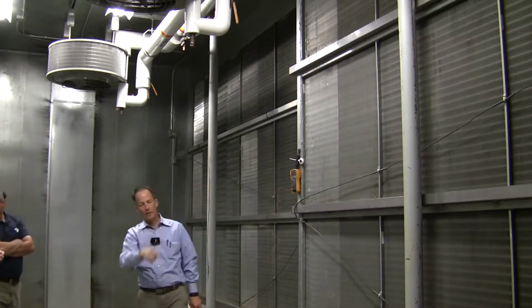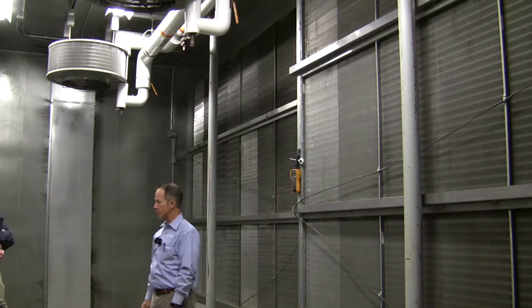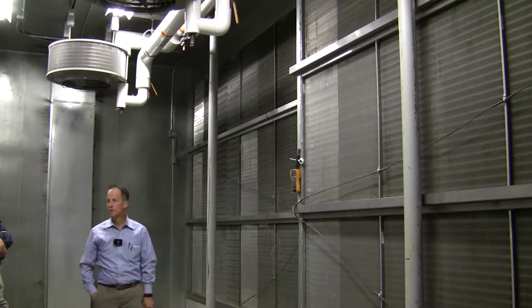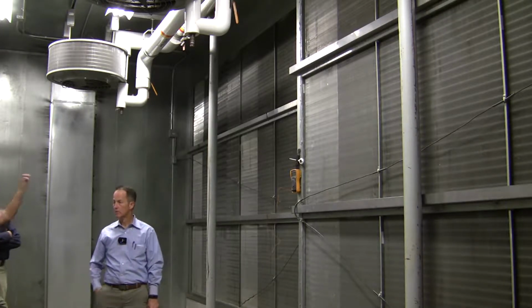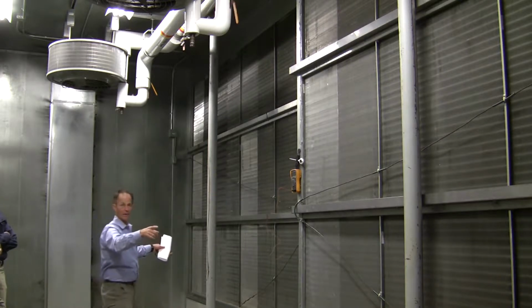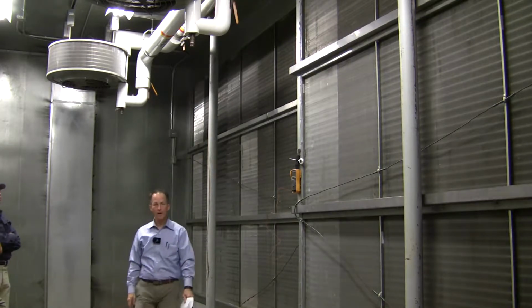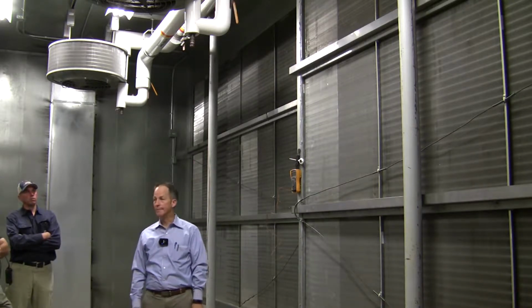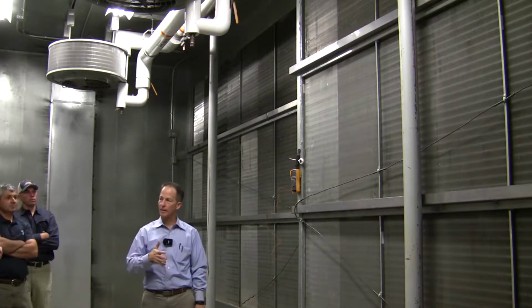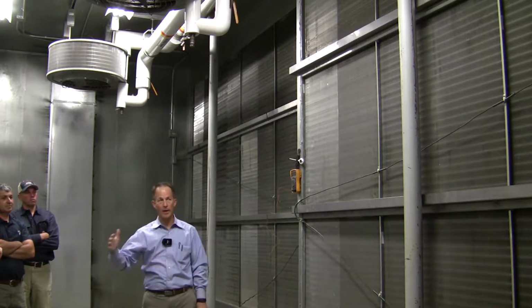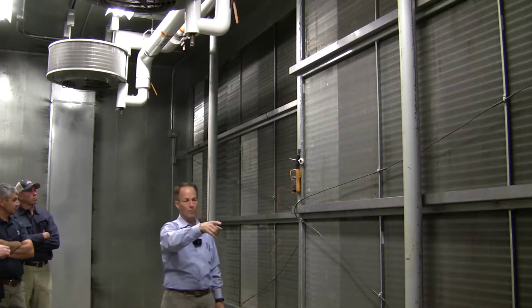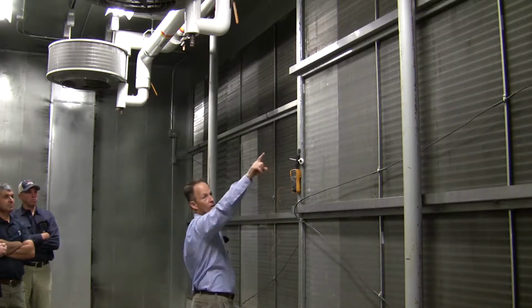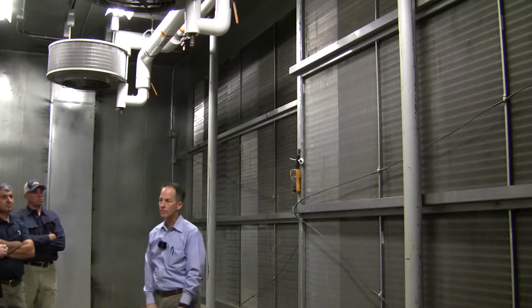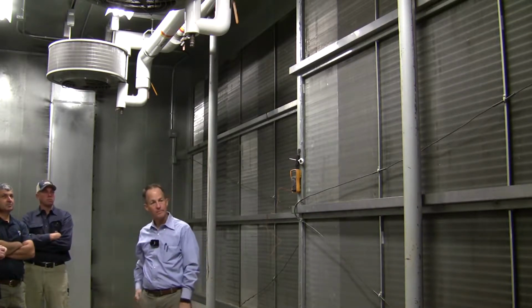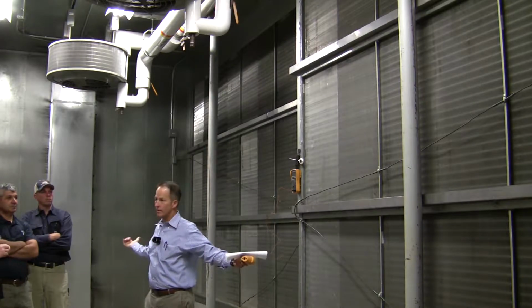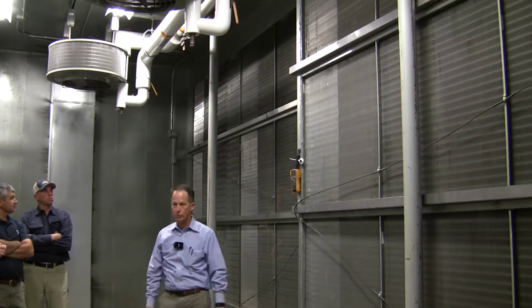All right, so we've got our sensor here. Where's our cooling coil discharge sensor? Where should that be? It should be on the other side. Actually we have two of these, right? So we've got a sensor there, sensor here. It doesn't sense the top third. Right, but what are we most concerned about here? Our cold air on the bottom, right? So really, if there'd have been room, it'd have been better to run a sensor all the way across here and then go up. But again, we're catching this heat a little. We have freeze stats, hopefully on the other side.